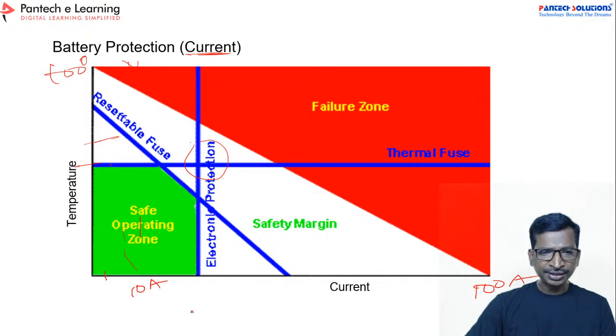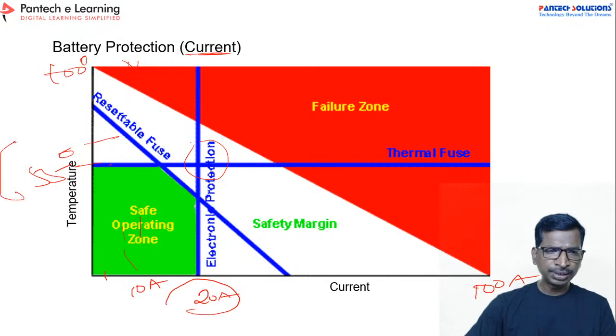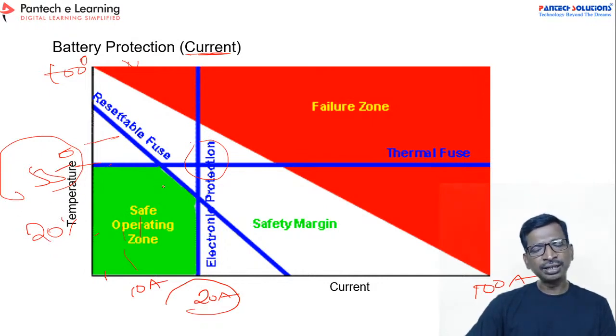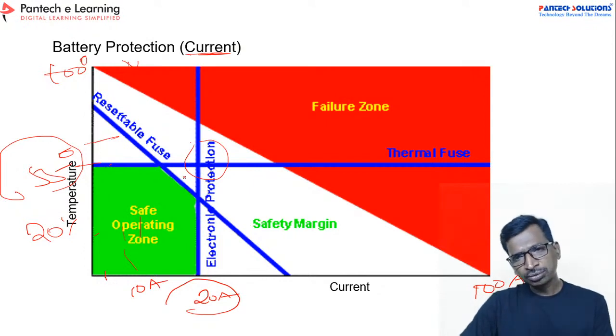Suppose your rated current is, let us assume, 20 ampere, right? And this is 55 degrees. In that case, all your tuning parameters should be less than this value only. Generally they will keep a 20% lesser value. So instead of 55, whenever it reaches 49 degrees itself, it will alarm you, right? So like that you have to form the logic, and then you have to identify your safer zone area.